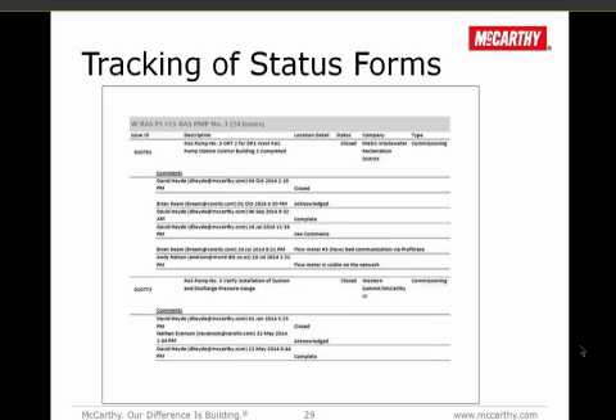On the specific project, it was a requirement that the owner had different levels of testing to do for the Profibus communications. One was just checking out the wires, then checking out after the instruments were connected, and then checking out the signals after all that was done.